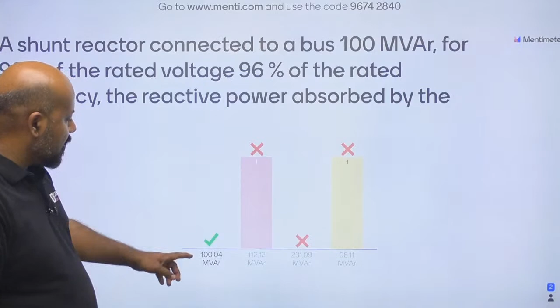Now please try to understand in this question what you have to do. Please remember, whenever an element is connected in series, how you are going to write the power with respect to the current. So you are writing current squared multiplied by the element resistance or the reactance, whatever you want, whether you want the real power or reactive power. If the element is connected in shunt, then what is the formula you are using? Voltage squared divided by the resistance or reactance of that element. You are talking about the reactive power. Yes or no? So you are going to write the reactive power as 3 times V phase square upon XL. XL is what? The reactance of the shunt reactor.